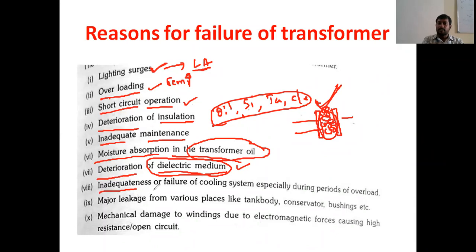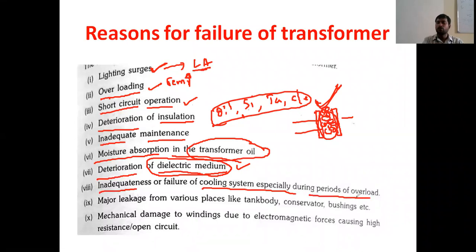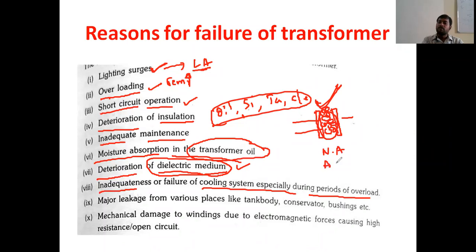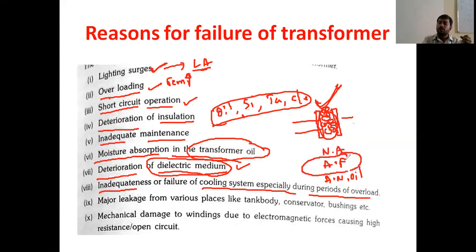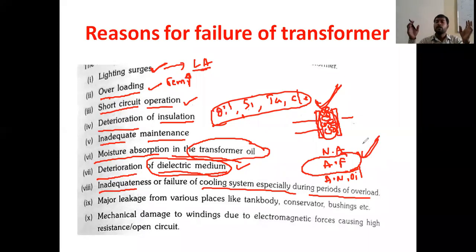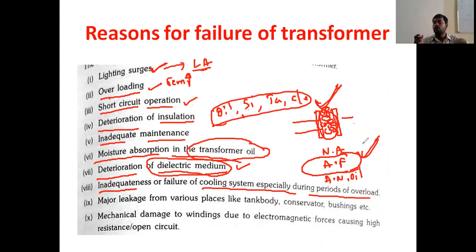Another reason is inadequateness or failure of the cooling system, especially during overloads. There are different types of cooling systems — natural air cooling, forced air cooling, and oil natural cooling. For high-capacity power transformers, separate fans are provided for cooling. If that fan fails during overloads, the temperature in the transformer increases and the transformer will fail.